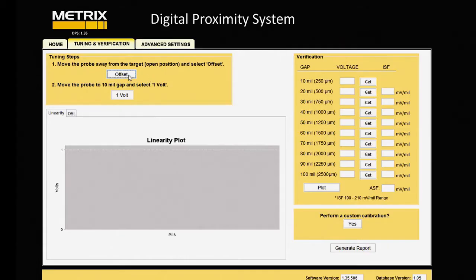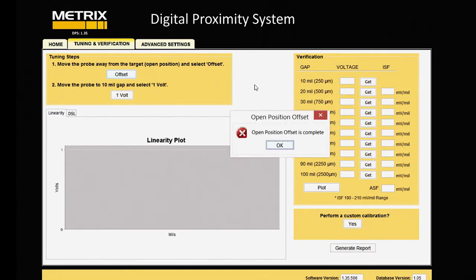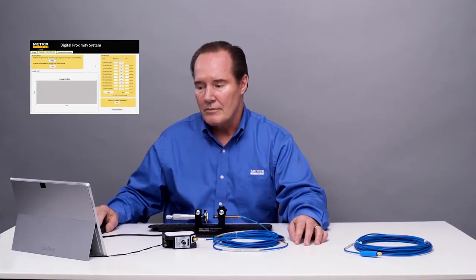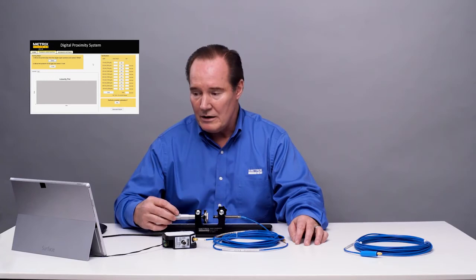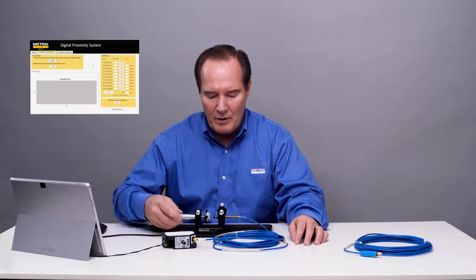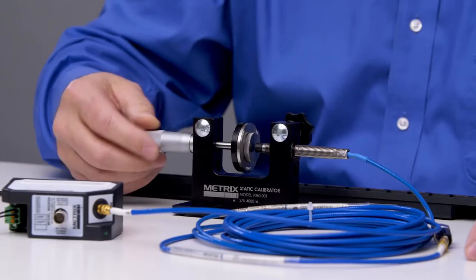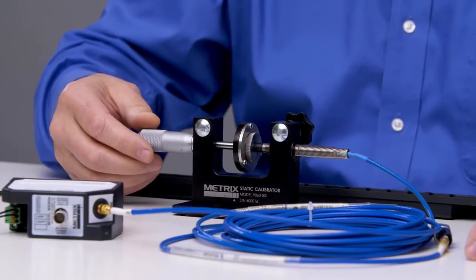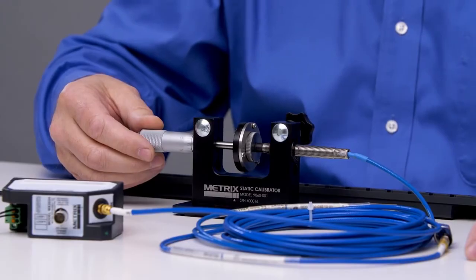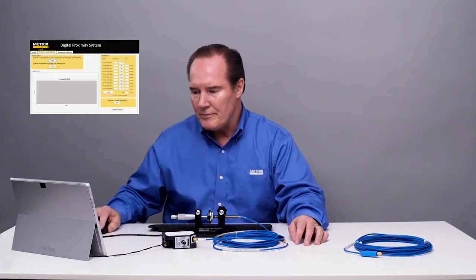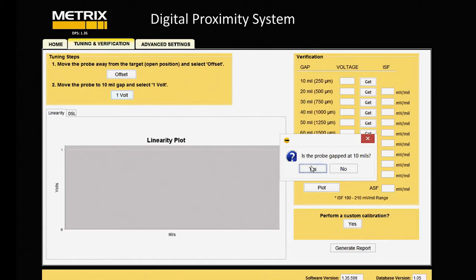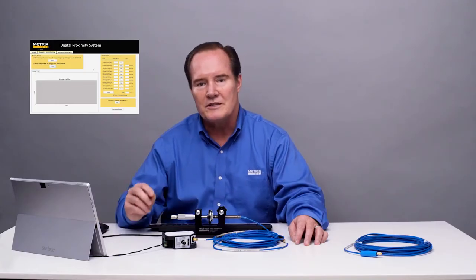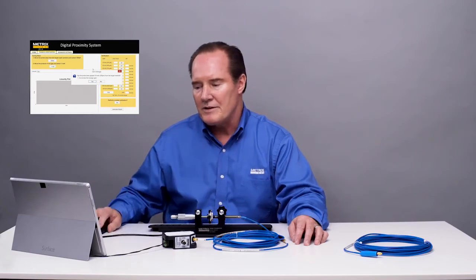And what I'll do is I'll say offset. And this really captures the top part of the curve. And then we'll go to a 10 mil gap and set the 1 volt to get the bottom portion, or where we want it to start. All right, and with that, I'll go ahead and move the dial micrometer to where we have contact, then I'll back it out to 10 mils. And we'll get a data point. So what we're doing here is we're setting where we want the curve to start. So we set it at 10 mils at 1 volt, because that's what we want.